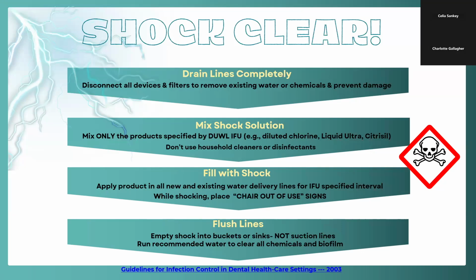Then you will mix the products according to the manufacturer's instruction and safety data sheets. Make sure you put on appropriate PPE before mixing and during application. Then you fill every water delivery line with the shock solution for the specified time interval. Immediately place chair out of use signs on the unit to prevent injuries to patients or staff. Finally, empty the shock solution into a bucket or sink.